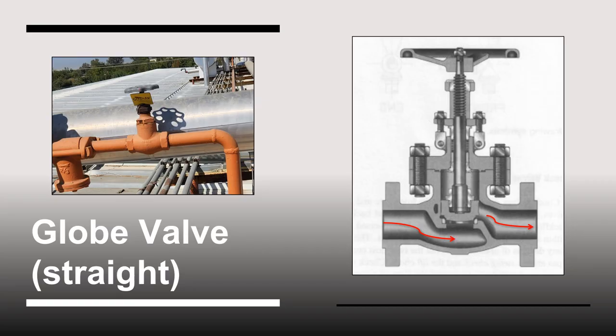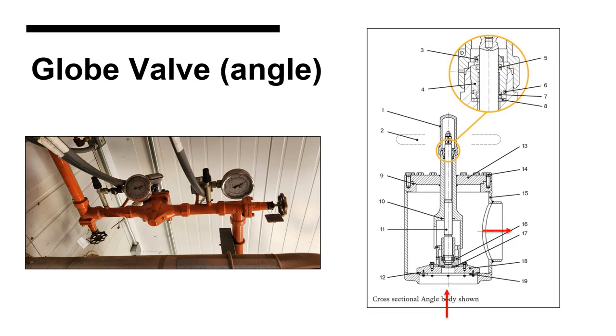Straight globe valves are common in refrigeration systems and are largely used for controlling flow by allowing or stopping it. Typically, the flow direction through a globe valve is against the plug. Globe valves should not be used to throttle the flow of fluid; instead, they are either fully open or fully closed and require multiple turns to operate. Angled globe valves are just as common and are used for the same purpose.